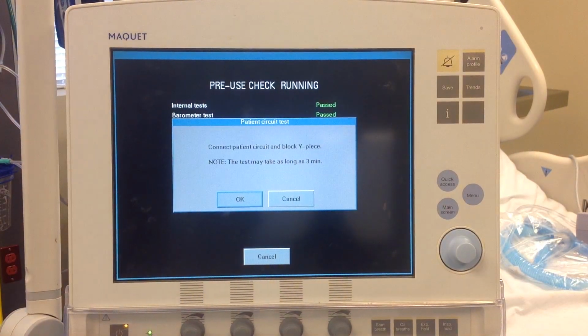One thing on the Maquet that you would want to do is go ahead and use a bacterial static, viral static filter on the exhalation side. There is nothing filtering the expiratory gases coming out of the patient. So you would want to do it. Maquet will tell you that if you do that, you can actually increase the rain out in the expiratory filter, only because the exhalation cartridge is heated, and with that expiratory filter you will drop another 2 degrees centigrade in your exhalation gas, which will cause rain out.